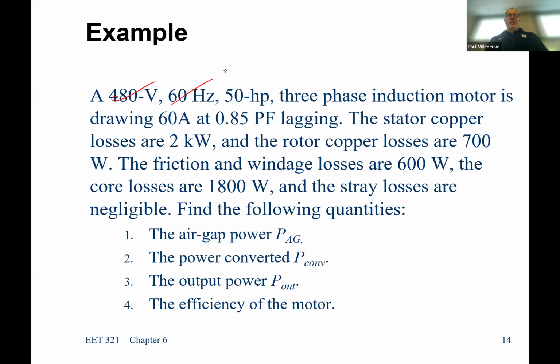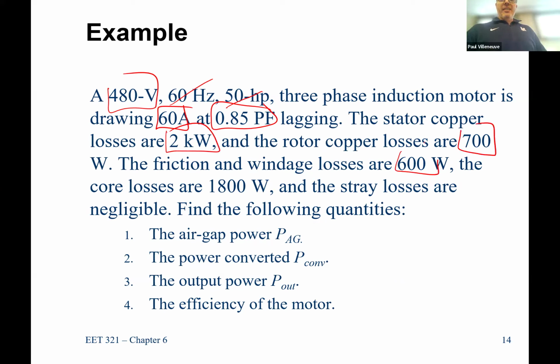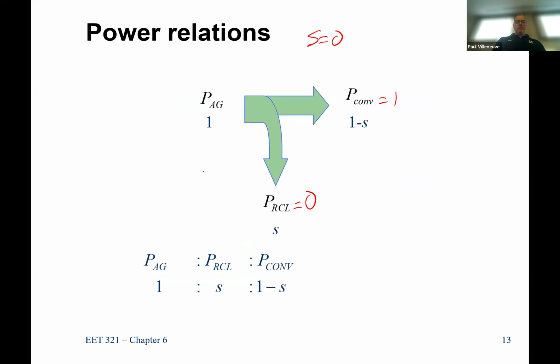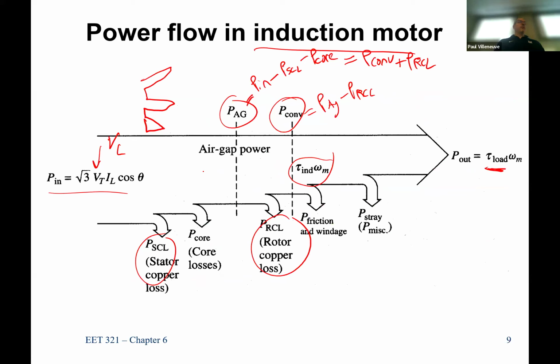So we don't really need the 50 horsepower figure. We definitely need the current and the voltage, and technically we do need power too, since we'll calculate P—so I misspoke earlier. We need the 2 kilowatts of stator copper loss, and we need the other loss terms. So all you need to do this problem is start from P-in, subtract all those loss terms, and you get your answer.